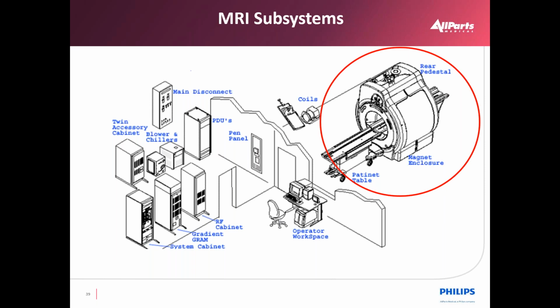Starting in the scan room or magnet room, we have the main magnet enclosure, which houses the superconducting magnet, the radio frequency coils, the gradient coils, and a cooling or refrigeration system. The superconducting magnet generates the static magnetic field required for polarization or alignment of the body's protons. The cooling system surrounds the magnet and maintains it in a bath of liquid helium at 4.2 degrees Kelvin, or minus 452 degrees Fahrenheit.